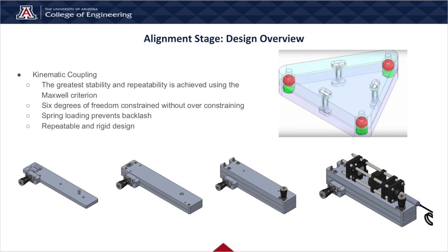The bulk of the mechanical design work was focused on the transmitting laser alignment stage, also referred to as TX. This sub-assembly is what determines the alignment capabilities of the system, so it was important to make sure that it was robust. This design was based around kinematic coupling and spring loading so the alignment stage could be as rigid and repeatable as possible.